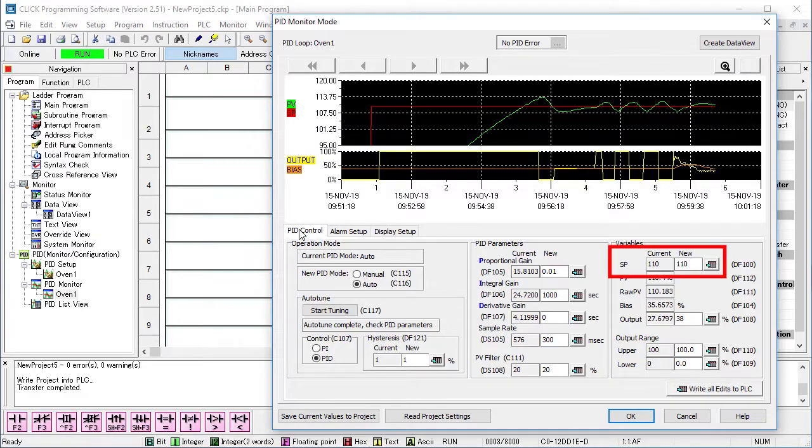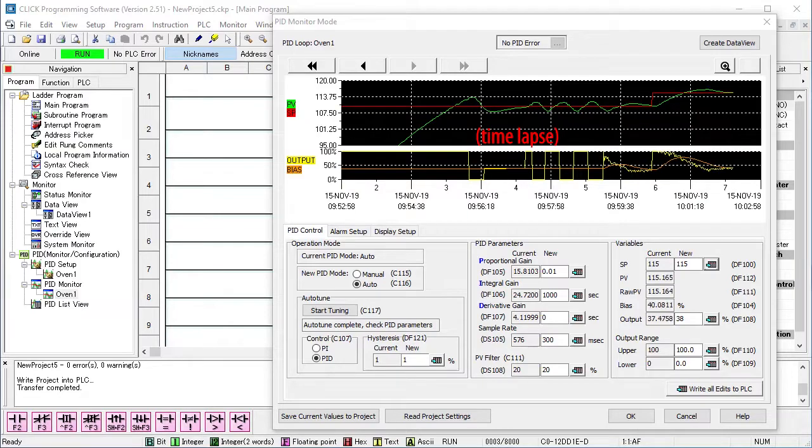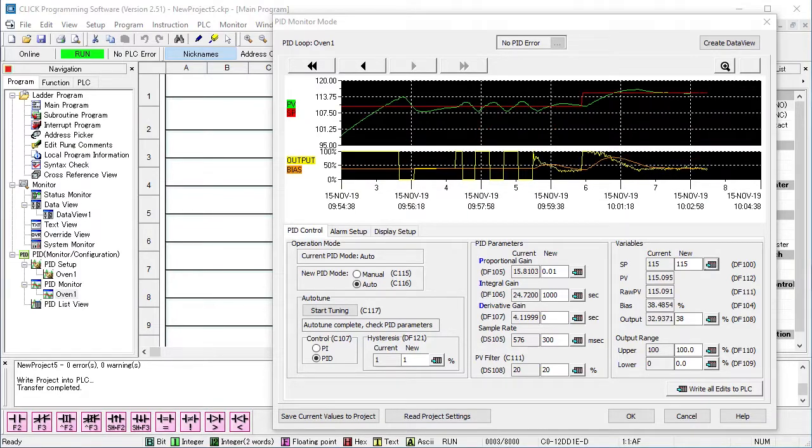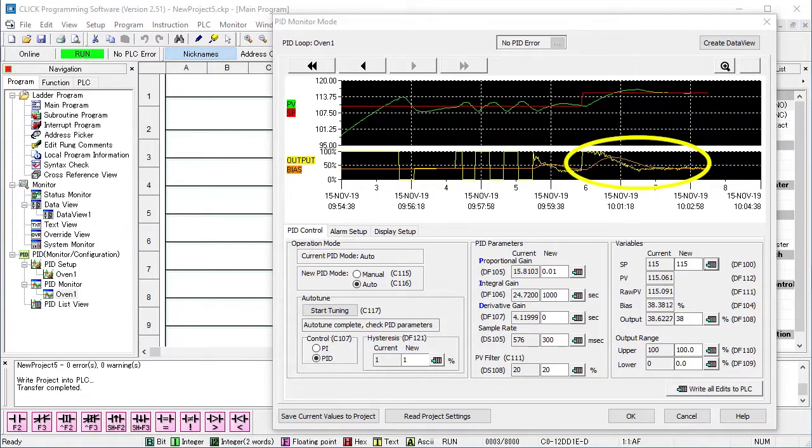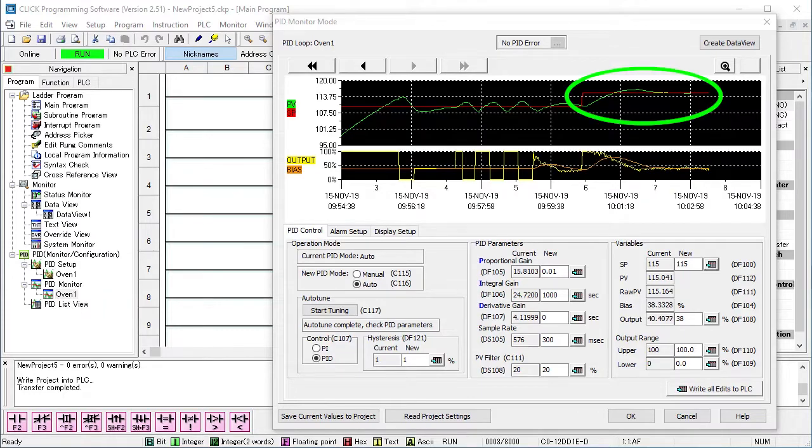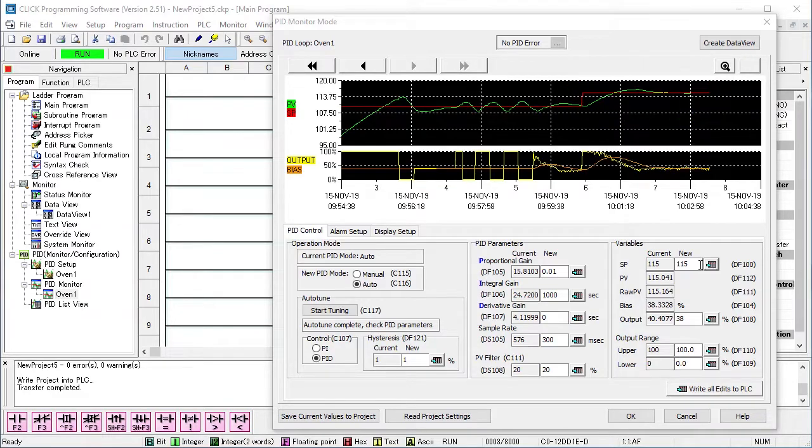Let's bump the set point up 5 degrees and fast forward the video. And we see PID automatically adjusted the control output to get our process to the new set point quickly and efficiently with just a little overshoot. Exactly what I want to see.